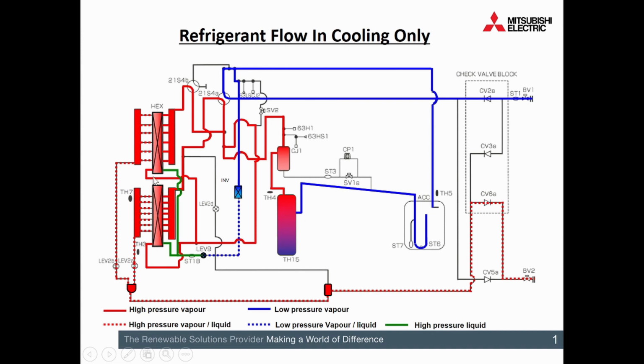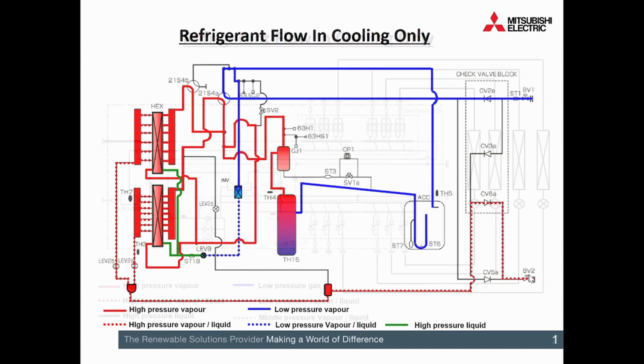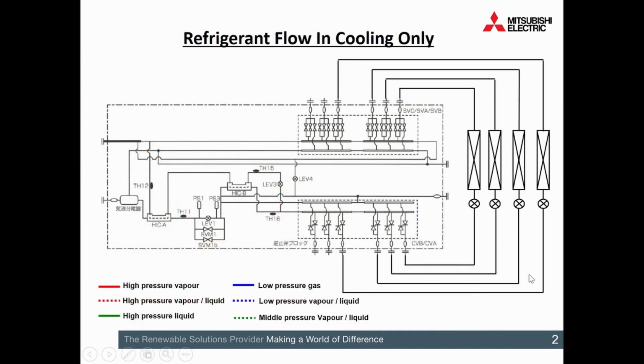By the time that refrigerant's passed through that coil, it will have gone from being a vapor to all being a liquid with a little bit of subcooling. Not much, like maybe 1 or 2 degrees, if that. That refrigerant's passing from there and off past my check valves and off to the BC box. I'll come back to the rest of the circuit in a second. So there's that refrigerant passing into the BC box. So this bit here is my BC box. And then I'm showing 4 indoor units here just to give you an idea.